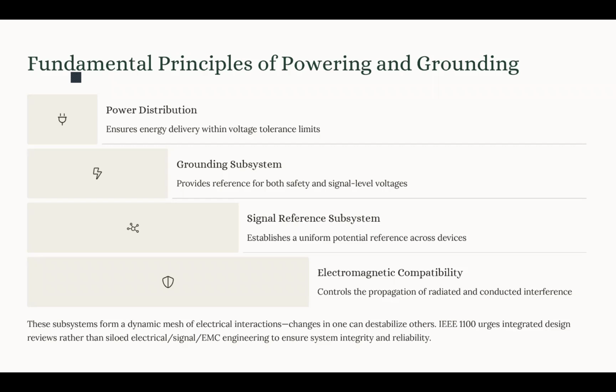The next subsystem that we mention is the grounding subsystem. This subsystem provides the reference point for both safety and operational voltage. In IEEE 1100, grounding is not just a safety feature; it is also a functional infrastructure element for sensitive electronic devices. One of the requirements is ground impedance, which should be less than 1 ohm from the equipment to the signal reference grid, and less than 1 milliohm at radio frequency in high-speed digital systems.